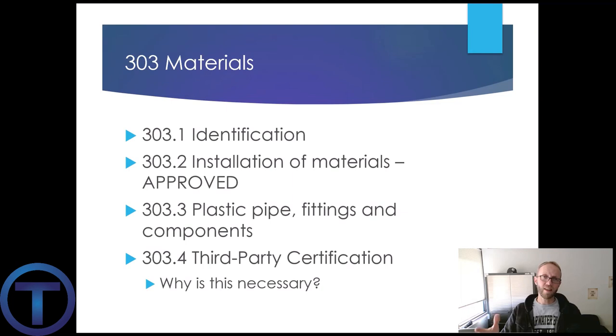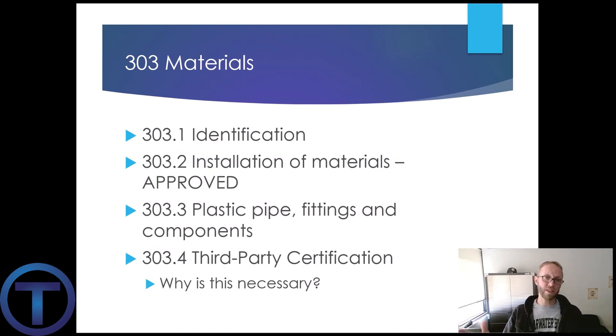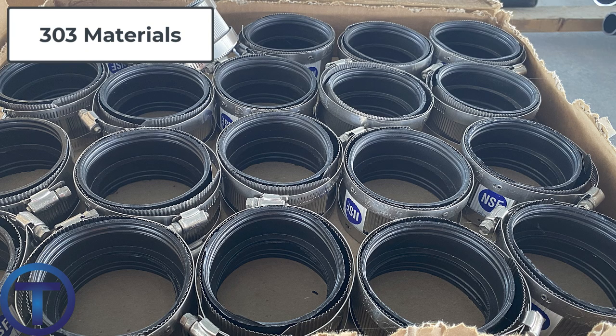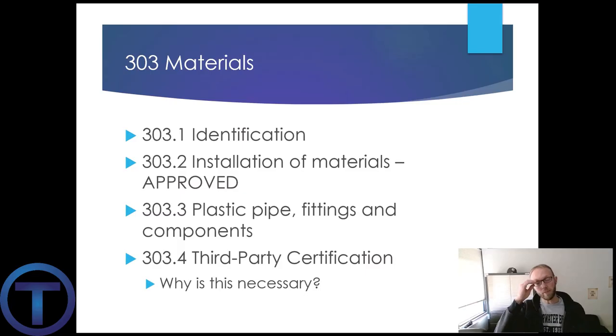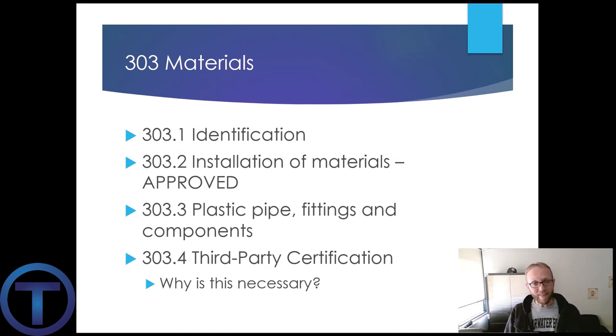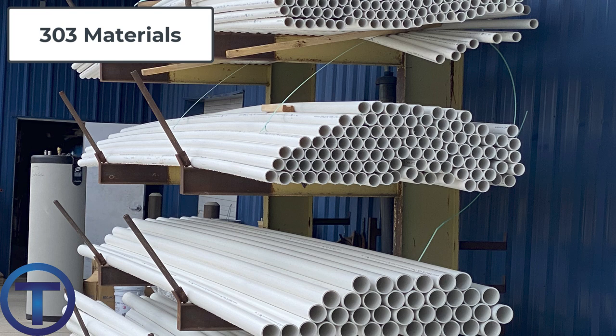303.1: materials have to have identification — meaning the manufacturer's markings and referenced standards so they can prove it's a quality piece and it's approved for installation. They have to be approved for us to install them at all. And we are also required by 303.2 to follow the manufacturer's installation instructions — we need to install things the way they were designed to be installed. 303.3: plastic pipe, fittings, etc., require third-party certification, same as 303.4.